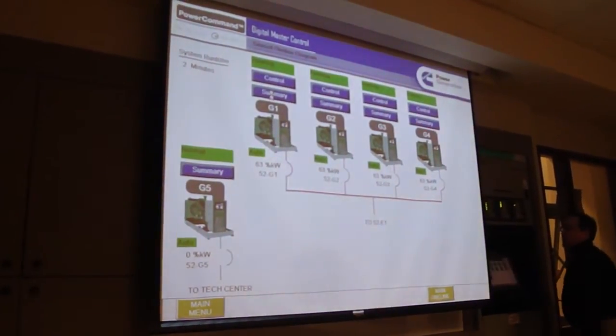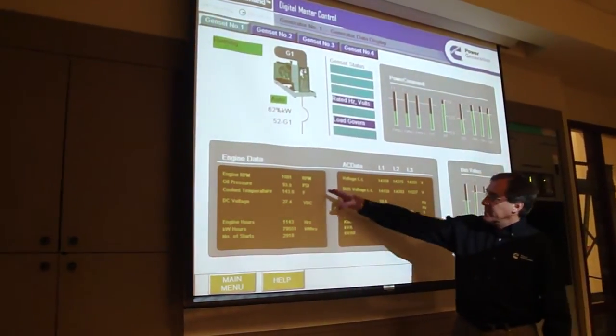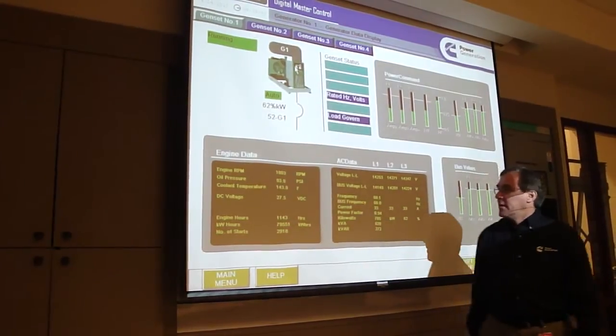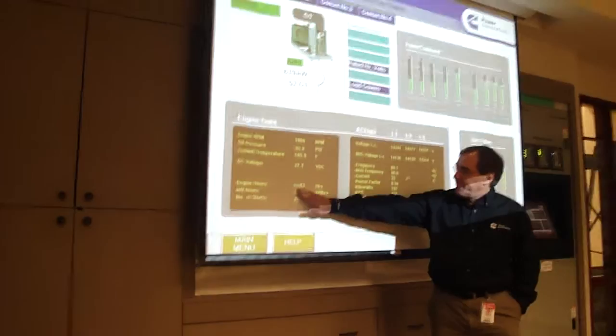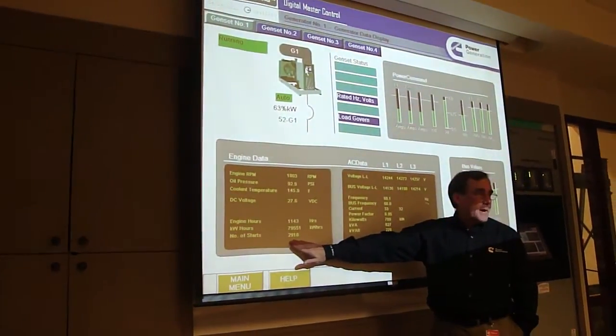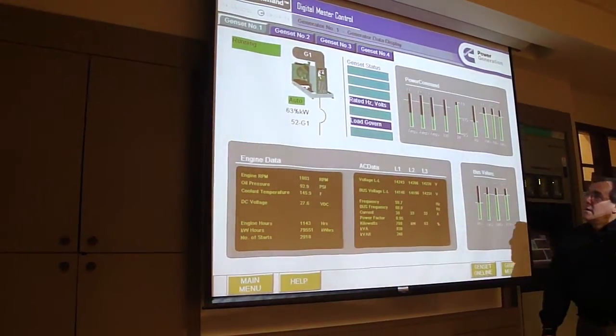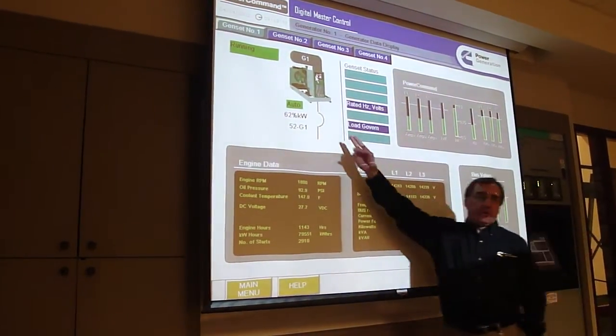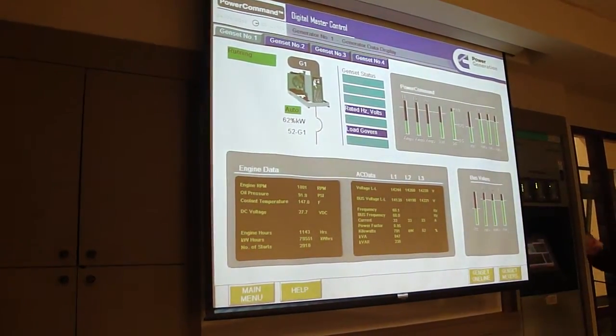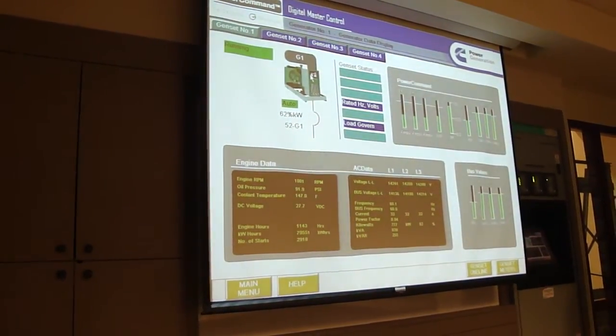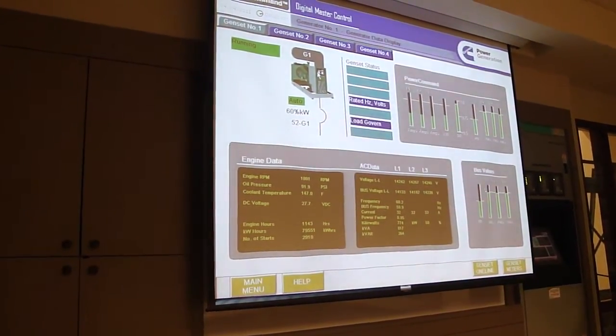We can look at any one generator and see some statistics and data from that generator — speed, oil pressure, cooling. Here's an interesting thing: this engine has 1,100 hours on it. It's been started almost 3,000 times in demonstration, which means this breaker has got 3,000 operations on it.